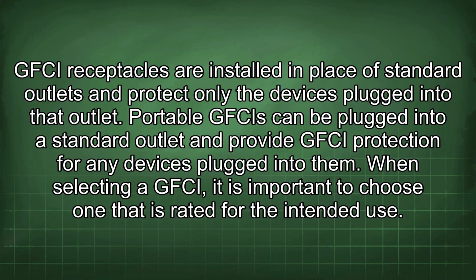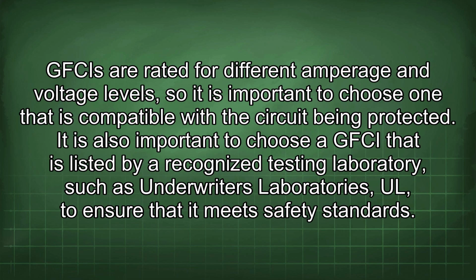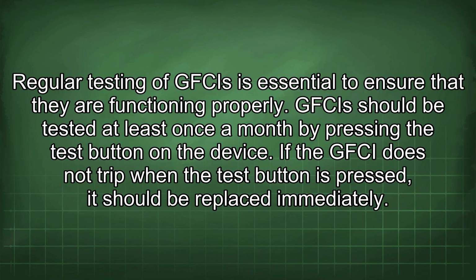When selecting a GFCI, it is important to choose one that is rated for the intended use. GFCIs are rated for different amperage and voltage levels, so it is important to choose one that is compatible with the circuit being protected. It is also important to choose a GFCI that is listed by a recognized testing laboratory such as Underwriters Laboratories, to ensure that it meets safety standards. Regular testing of GFCIs is essential to ensure that they are functioning properly. GFCIs should be tested at least once a month by pressing the test button on the device. If the GFCI does not trip when the test button is pressed, it should be replaced immediately.